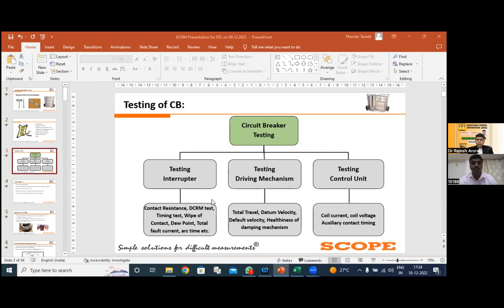Whenever we perform the contact resistance measurement, we get an idea about the healthiness of our static contacts. In the static contact resistance test, we keep our interrupter in the closed condition and inject a known amount of current through the contacts, where all the fingers are intact and your breaker is in the steady position. Whatever resistance value we get gives us an idea about the health of our static contact.